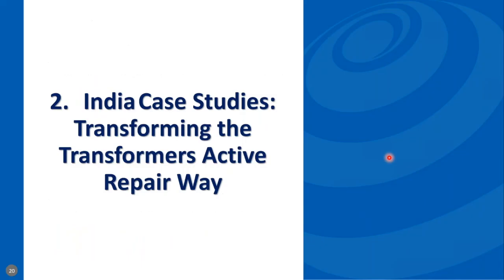The next and very important thing for the utility business is that the transformer is very expensive to replace for energy efficiency. It is not like a light fitting, where you replace the incandescent lamp with an LED at a lower, cheaper cost. So the cost of replacement of the transformer is very high. Mostly the utility has to get such cost approved by a regulator, and the regulator wants justification, and overall it increases the capex requirement of replacing this transformer.